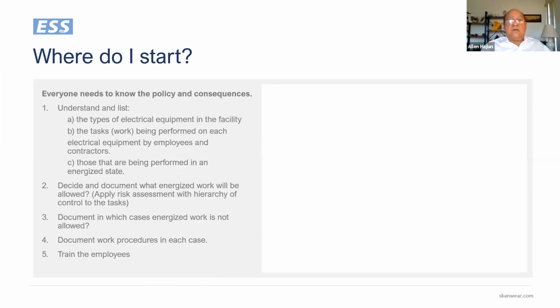So where do you start to create a good electrical safety program according to NFPA 70E or best practices? So you have to understand and list the type of electrical equipment in your facility, what tasks are being performed, and which ones are being performed in an energized state. When you have that, you can decide and document what energized work will be allowed, obviously applying the risk assessment and hierarchy of control, and document in which cases energized work is not allowed, and document those work procedures, and then you can train the employees.